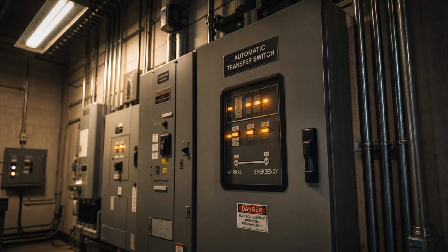This waiting is one of the quieter and more precise moments in the entire sequence. The transfer switch knows that the generator needs time to start, time to come up to speed, time for its voltage and frequency to stabilize at the values required before it can safely serve the building's loads. The transfer switch will not rush this. It will not connect the emergency source until that source is ready. And so there is a window of time, typically measured in seconds, sometimes 10 seconds, sometimes a few more, during which the building's emergency loads are without power. The corridors fed by the emergency system are dark. The critical panels are waiting. The transfer switch is holding, patiently and precisely, for the generator to become ready.